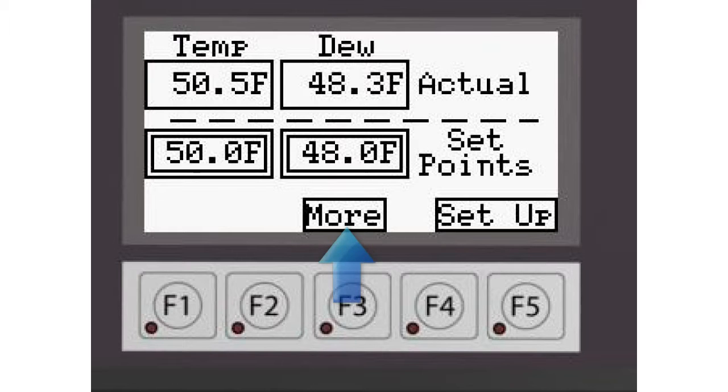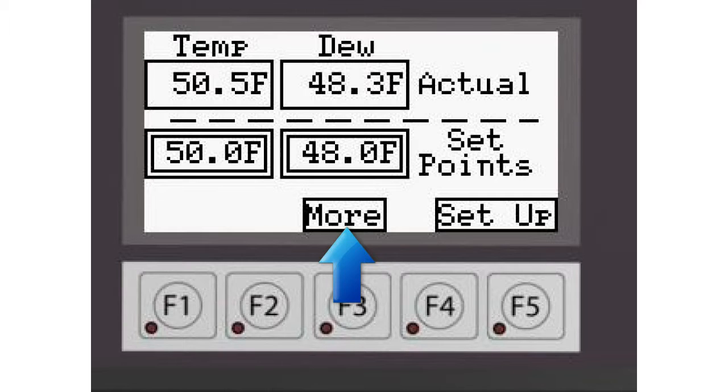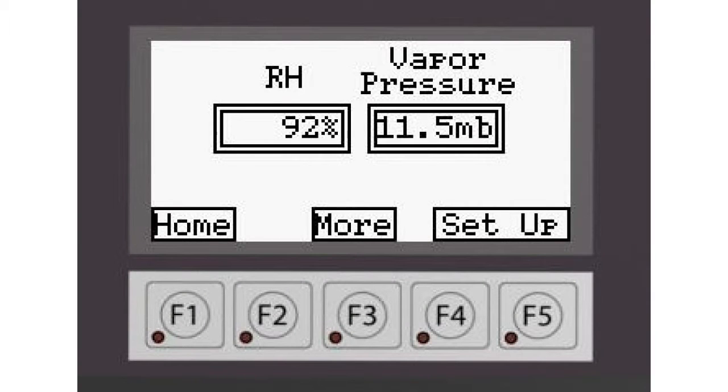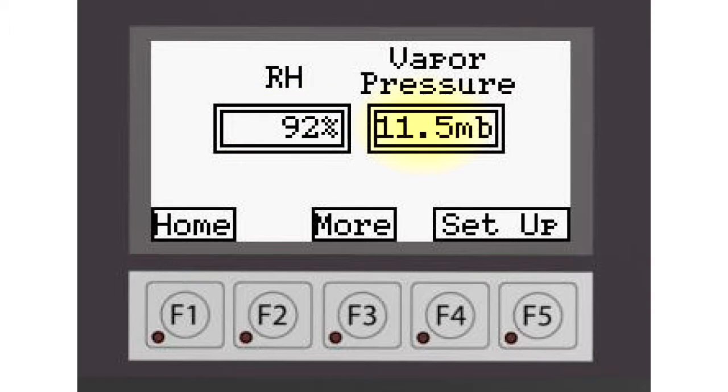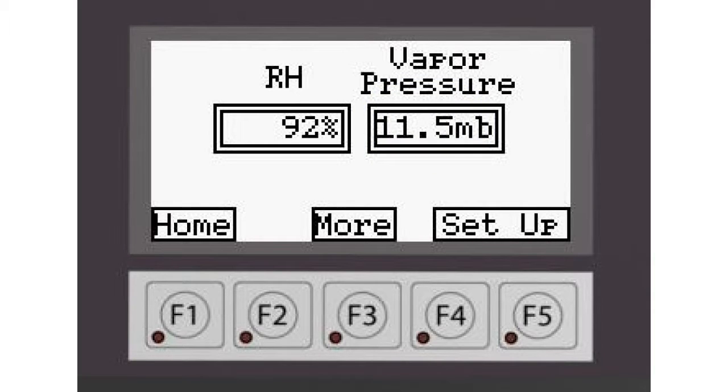Pressing the more button takes you to the next screen where you can see more information about what the control is doing. On this screen, you can see the relative humidity in the room on the left and on the right you can see what the vapor pressure is in the room expressed in millibars. This is the force of the water that would be exerted on the product that you have in the room.